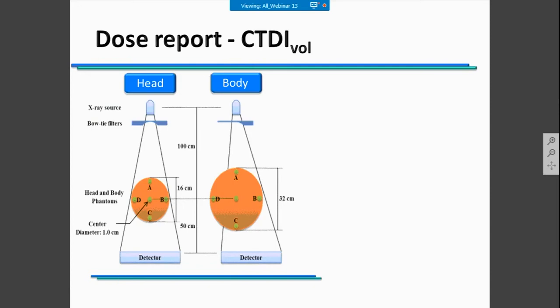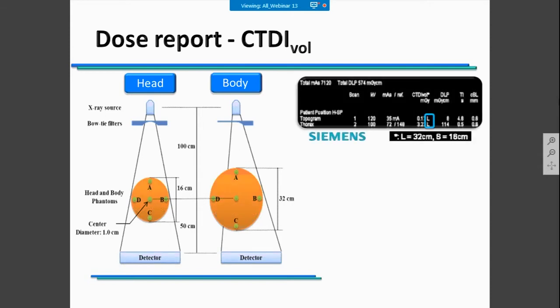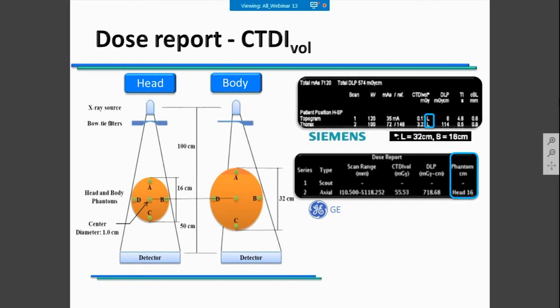It's important to know what kind of dose values we are looking at. We need to analyze what kind of CTDI vol is available on our CT scanner. For example, if you are using a CT scanner that represents the CTDI vol for body examinations, you should have the indication of the patient's size included. This is an example of the dose report from Siemens, indicating the size of the phantom.